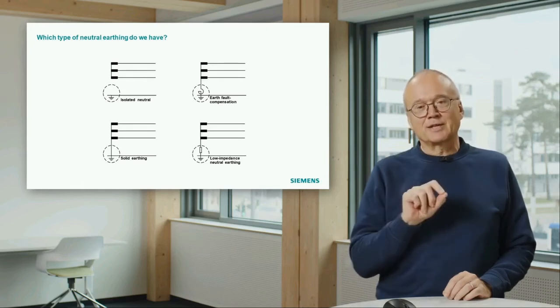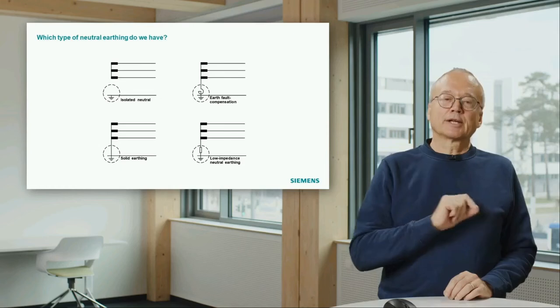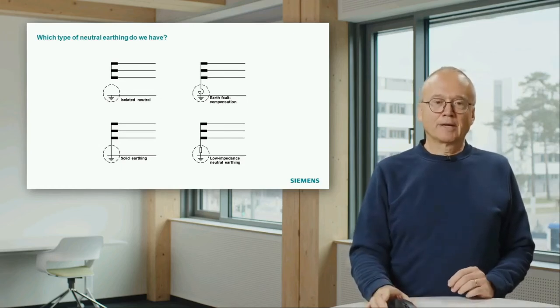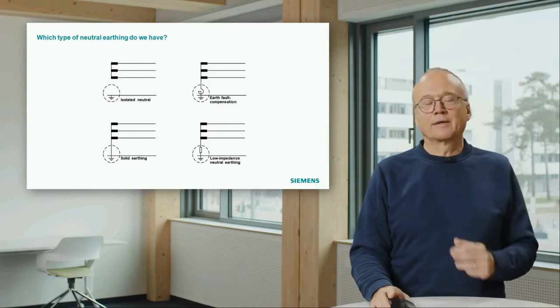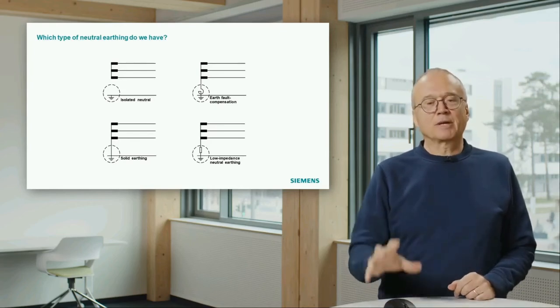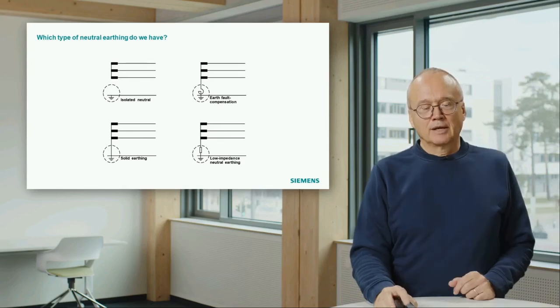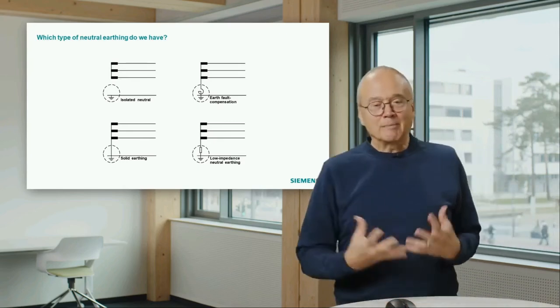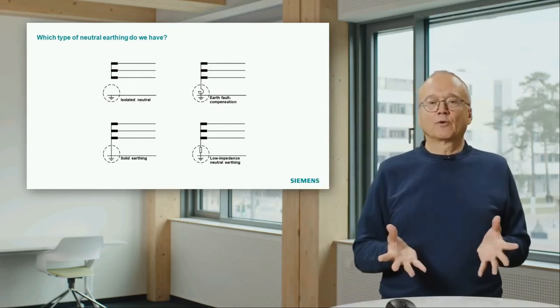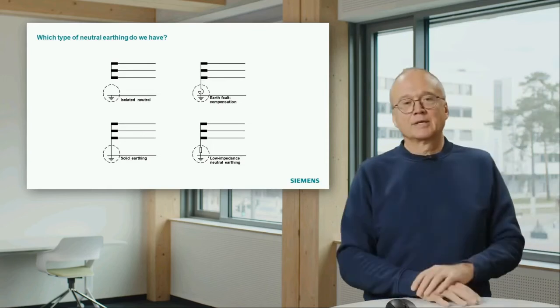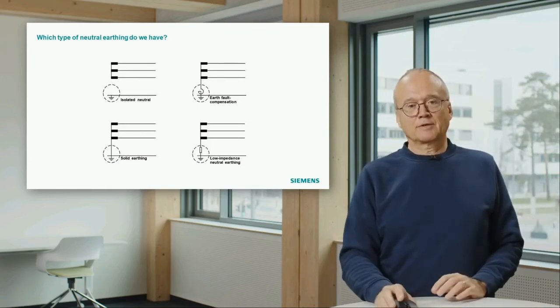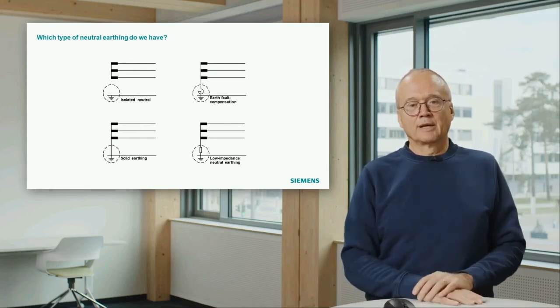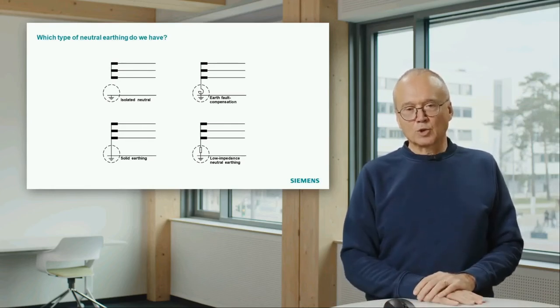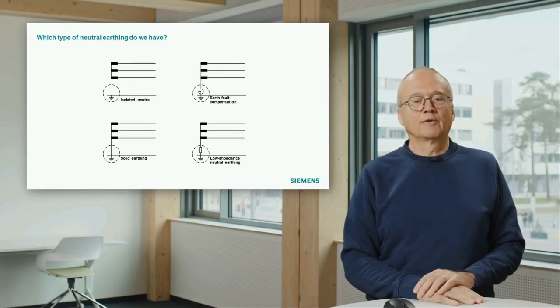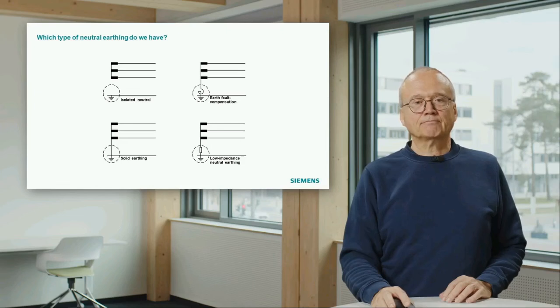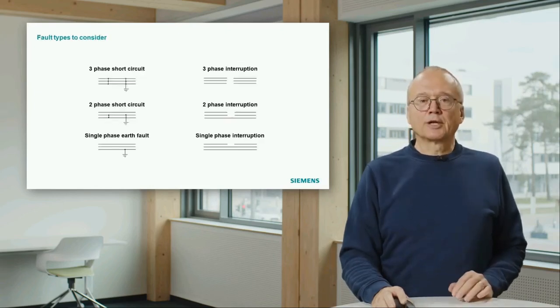That means in such a case, you must have additional protection functions to identify and find out where this type of fault is. So that is a special area of protection in these networks. That means if you think about a protection system for a network, you must have a look at this star point treatment. As I said, in a transmission system you are typically with solid earthing. In distribution and industrial systems, you find a lot of other different things. That was the neutral earthing.